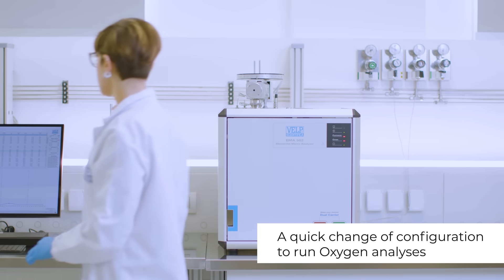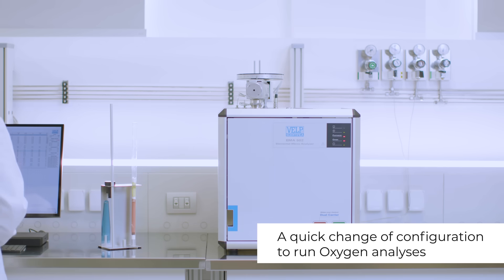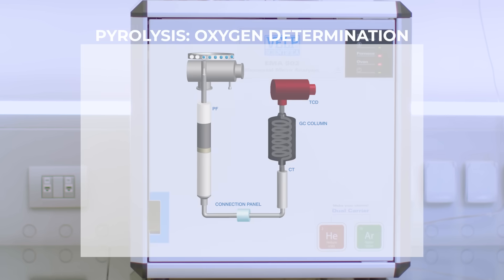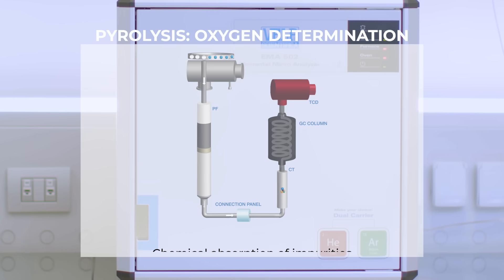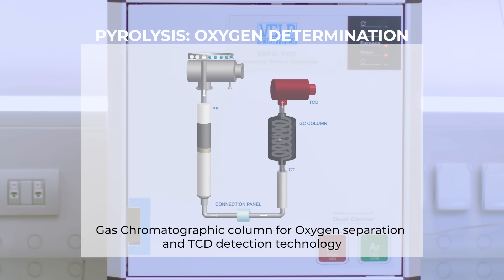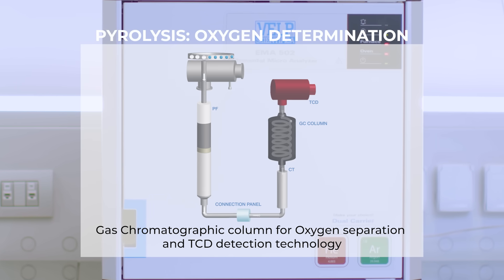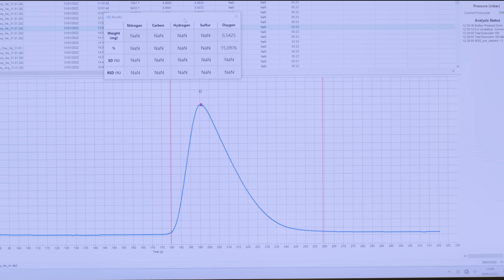To perform oxygen analysis, it is not necessary to have another instrument — just a quick and simple change of configuration and consumables. The sample is purged with the carrier and drops into the reactor, where high-temperature pyrolysis takes place. The flow then passes through a chemical trap to absorb all impurities before being conveyed to the gas chromatographic column and the TCD for oxygen quantification.